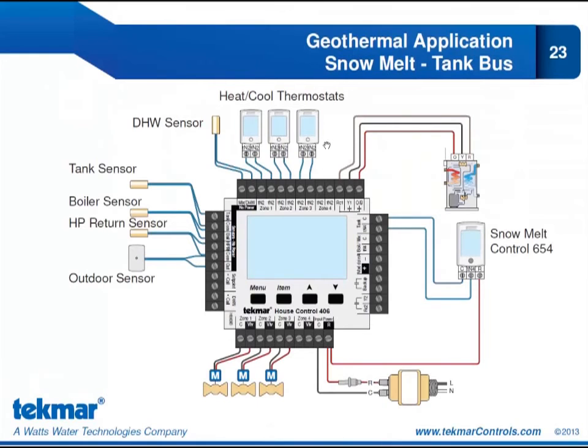So I have my 3 heat-cool thermostats connected to the onboard zones. Now because that's for radiant, and I only have 1 water temperature, I'm going to configure those zones to be tank zones. Now also on my tank bus, I have my snow melt. So I can connect my snow melt control 654 to the tank expansion terminals. Now I haven't shown you any of the outputs from this control, the pump outputs or the sensor inputs, and that was just to prevent this from looking too cluttered.